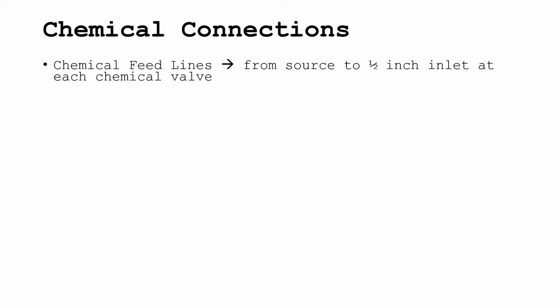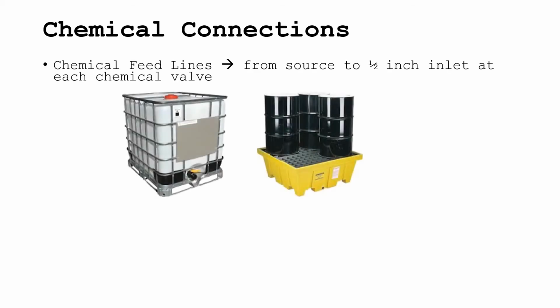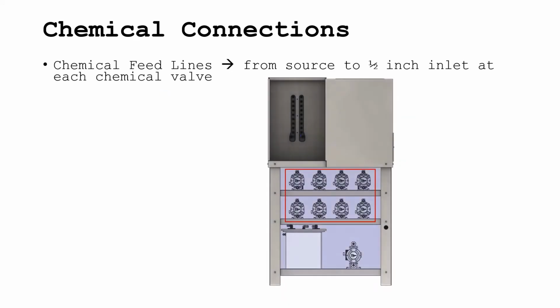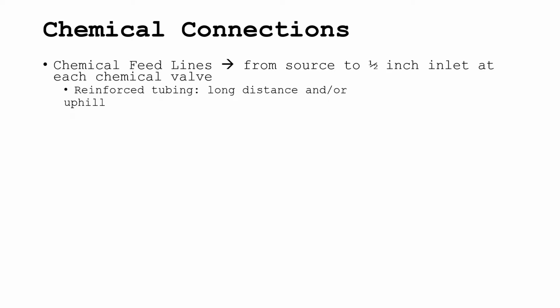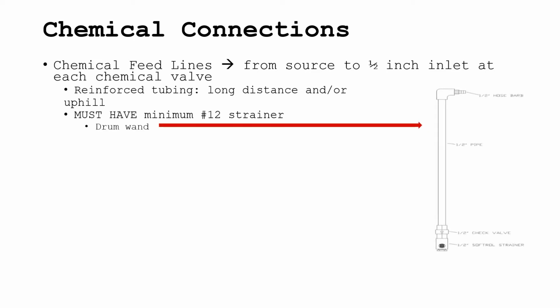Now, to complete the chemical connections, the chemical feed lines should run from the source, which would be a tank or a drum or some other storage unit, to the 1/2 inch inlet for each chemical valve. Reinforced tubing may be used on the inlets when the chemical is drawn a long distance and/or uphill. The inlet lines must have a minimum of number 12 mesh strainers. These may be incorporated with drum wands, available from Softrol, or can be plumbed in-line.